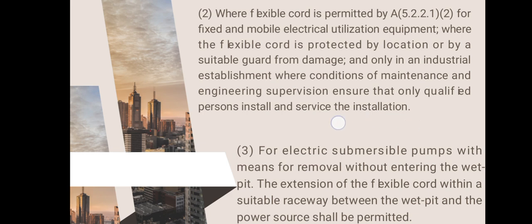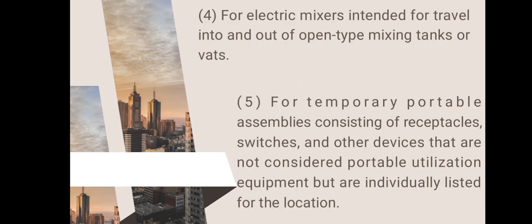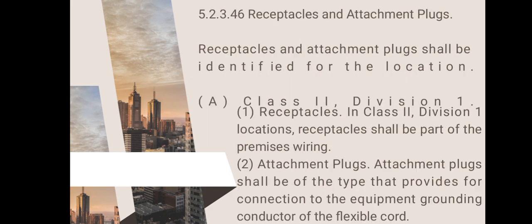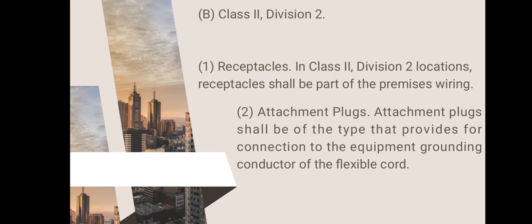For Division 2 of Class 2, locations where combustible dust is not normally in the air in sufficient quantity to produce explosive or ignitable mixtures, but where dust accumulations may be sufficient to interfere with the normal operation of electrical equipment. The wiring methods of Class 2 Division 2: all wiring methods permitted in Division 1, rigid metal conduit, intermediate metal conduit, electrical metallic tubing, and dust-tight wireways.